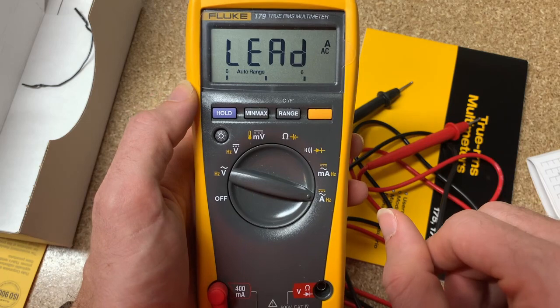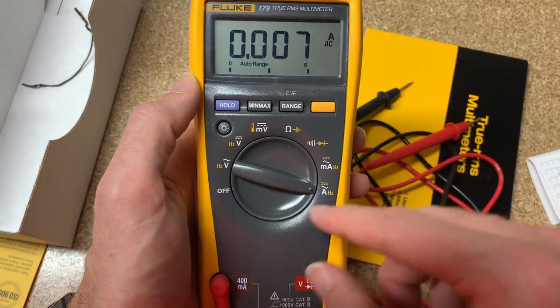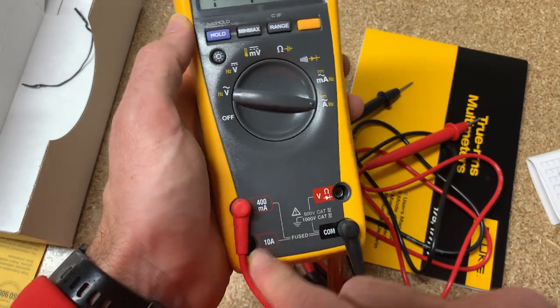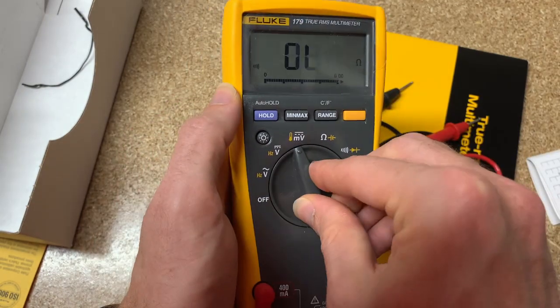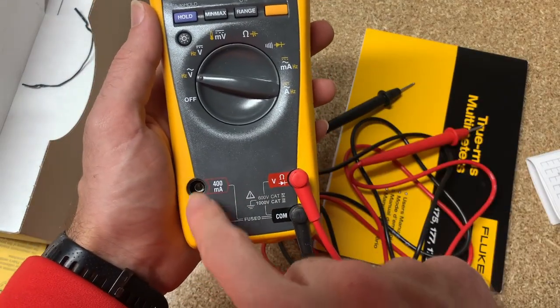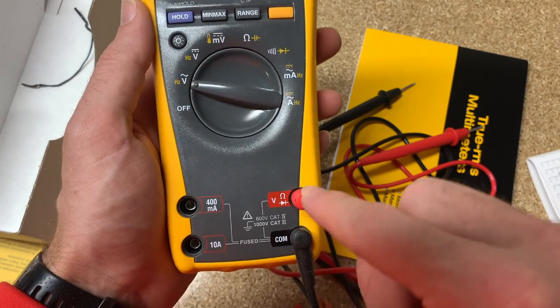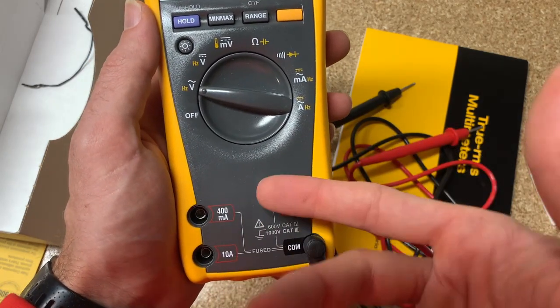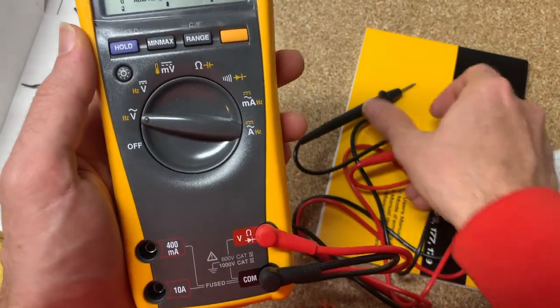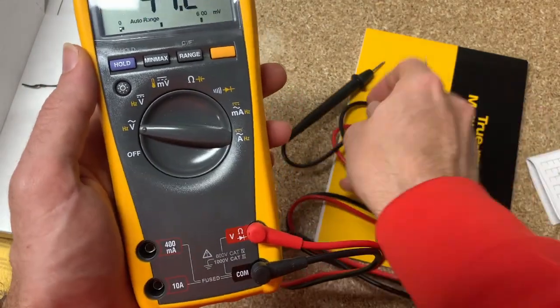And then next one, same exact thing, except higher range. Instead of milliamps, you get full amps up to 10 amps if you're using this port. Another thing to do, I can show this. I'll plug it back into multimeter. If you have used current and you get over here and you go back to voltage, you always have to bring these back over here. It's not a safety hazard because these are fused, so the meter will protect you, but you will be replacing fuses if you try to measure voltage after having your test leads plugged into the amp ports.